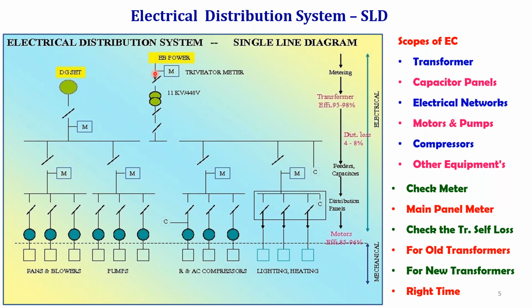Electrical power coming inside the plant, automatically a main energy meter is placed to measure the energy consumption. Now the transformer efficiency is going to be almost 99%, so there is a little scope for energy saving in the transformer. But whenever the transformer is very old, or has some fault record, then there is a scope for improving the efficiency, and similarly for energy conservation also.